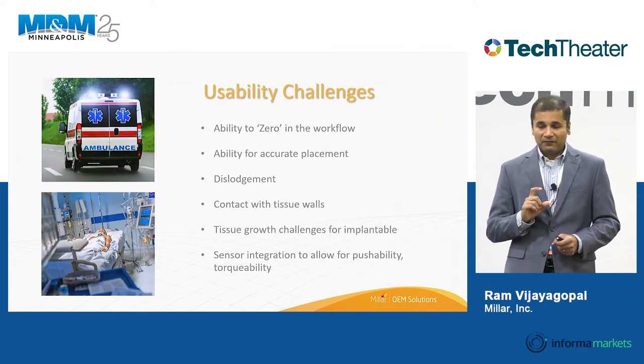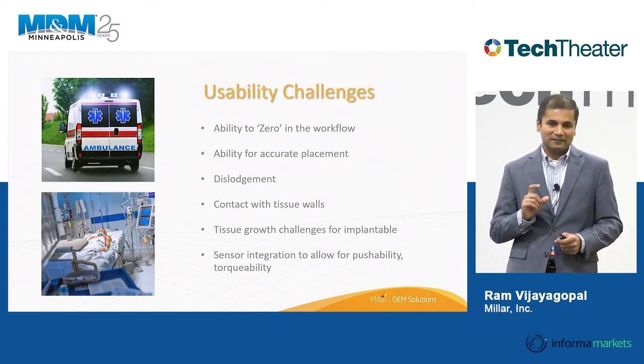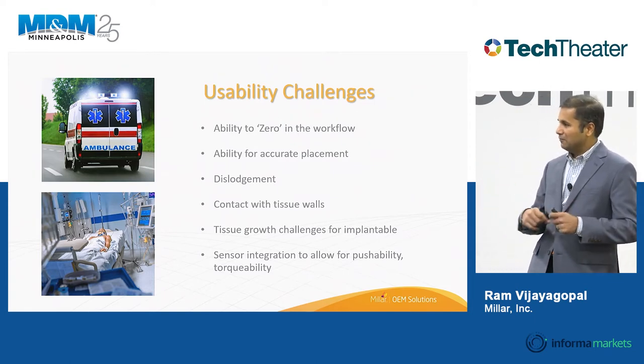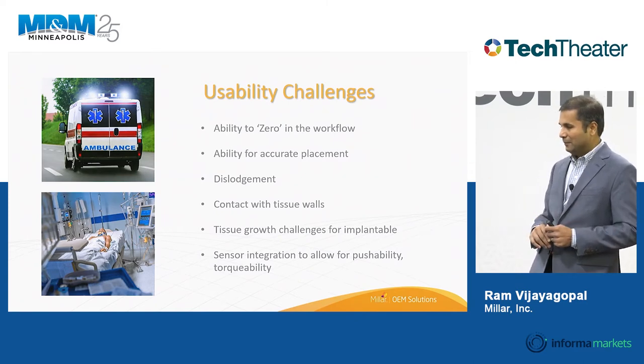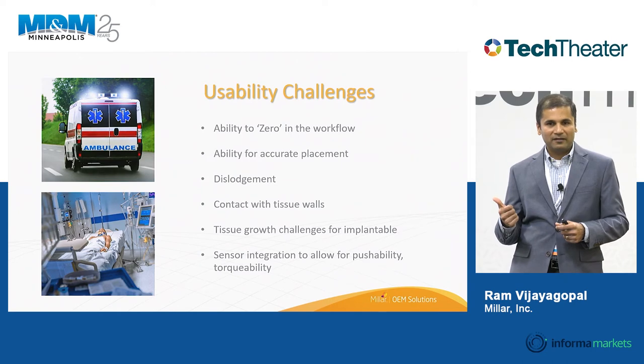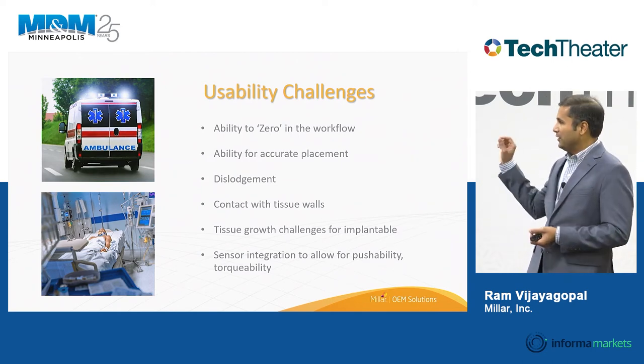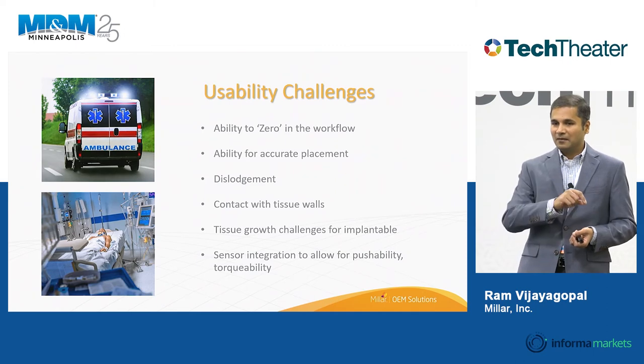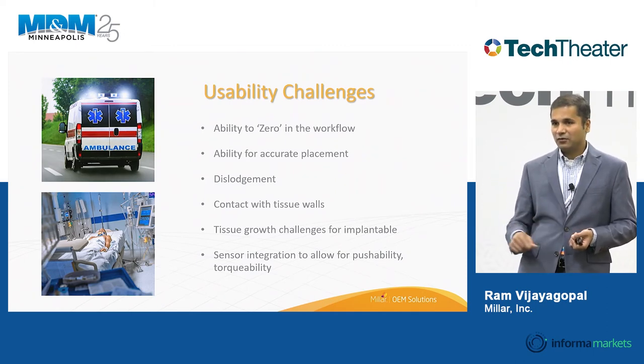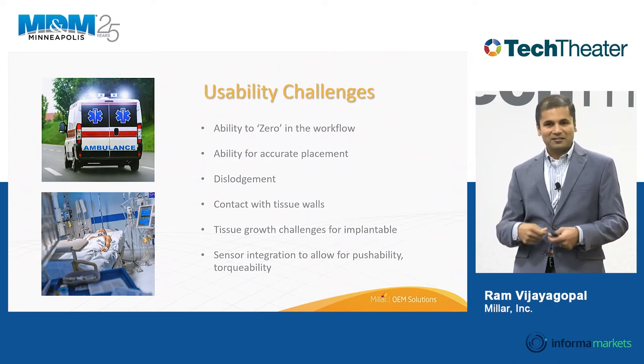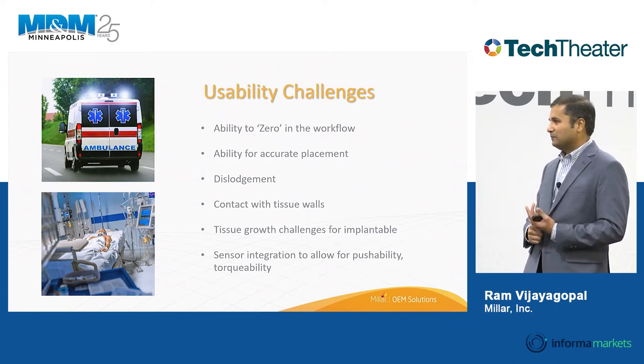Usability is a very important area that gets very little attention. For example, if you can't zero the sensor, you won't get good readings — the workflow must allow adequate zeroing. It might take five to ten minutes, or in emergency applications where they open the sensor and immediately go inside a patient, there's no time for that. So you have to build your workflow around proper zeroing.